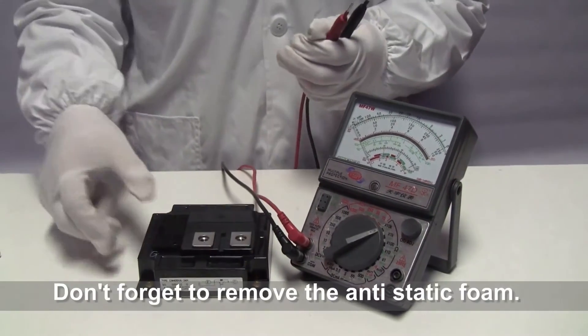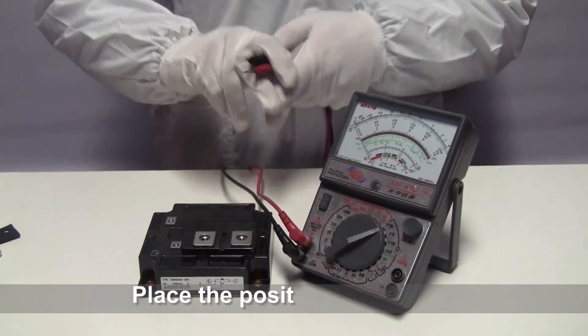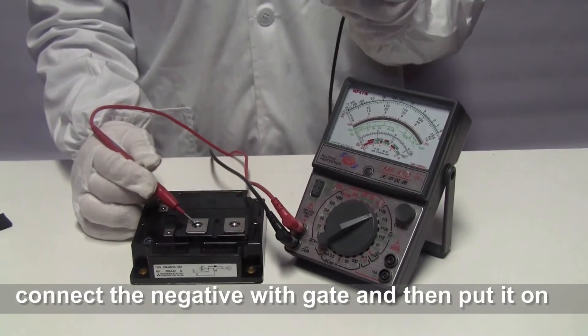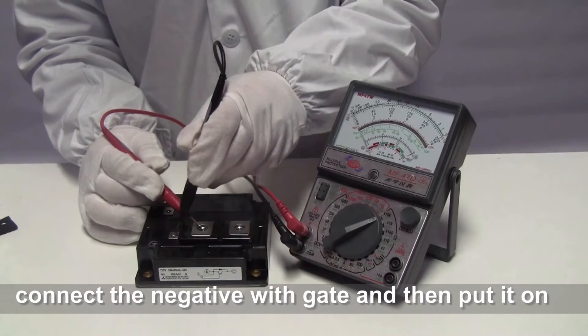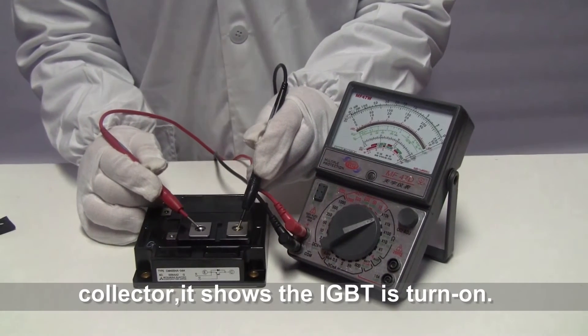Don't forget to remove the anti-static foam from the IGBT module. Place the positive probe on the emitter. Connect the negative with the gate, and then put it on the collector. It shows the IGBT is turned on.